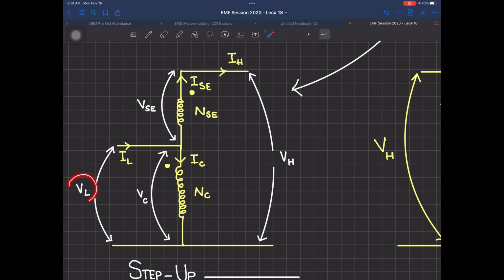I have my low voltage, which will be 13.2 kV. This is going towards a common winding, and this is going over here. So I have VL and VC as the same. What is VC? This is the common winding voltage. Why common? Because it is available in the primary and also in the secondary. That's why it's called the common winding.